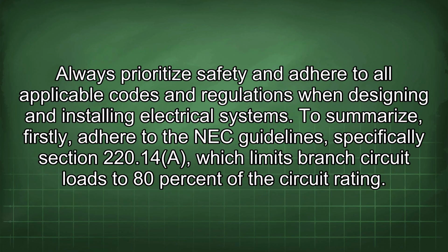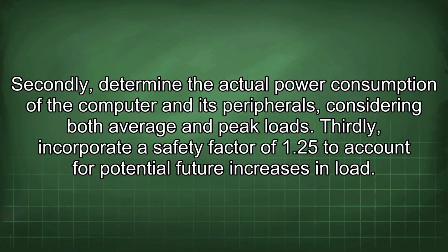Always prioritize safety and adhere to all applicable codes and regulations when designing and installing electrical systems. To summarize, firstly, adhere to the NEC guidelines, specifically Section 220.14a, which limits branch circuit loads to 80% of the circuit rating. Secondly, determine the actual power consumption of the computer and its peripherals, considering both average and peak loads. Thirdly, incorporate a safety factor of 1.25 to account for potential future increases in load.